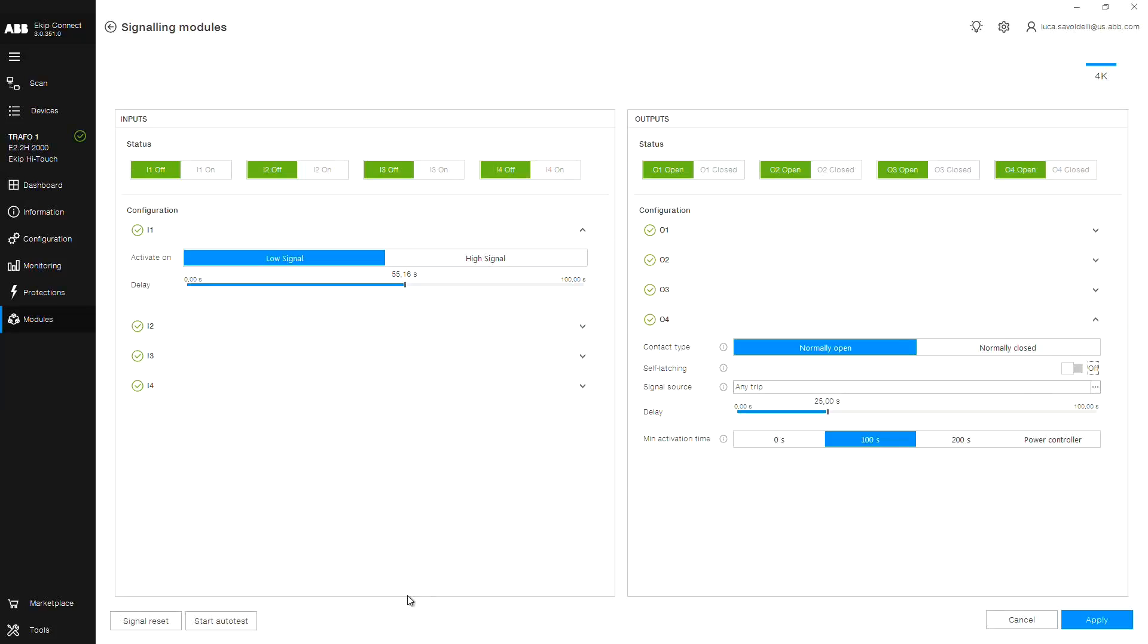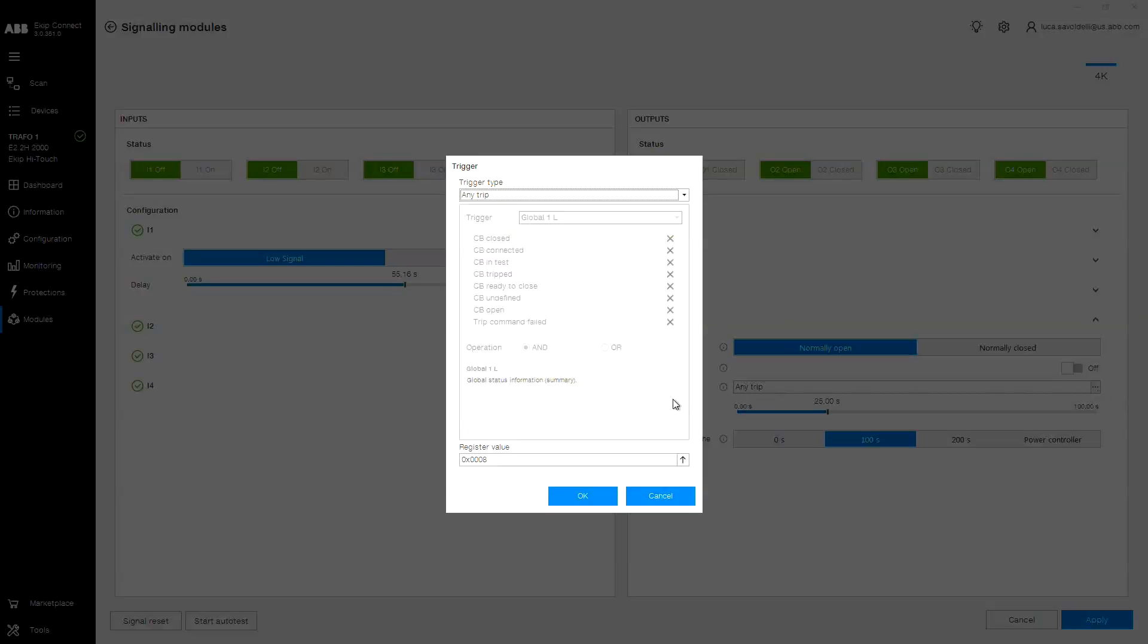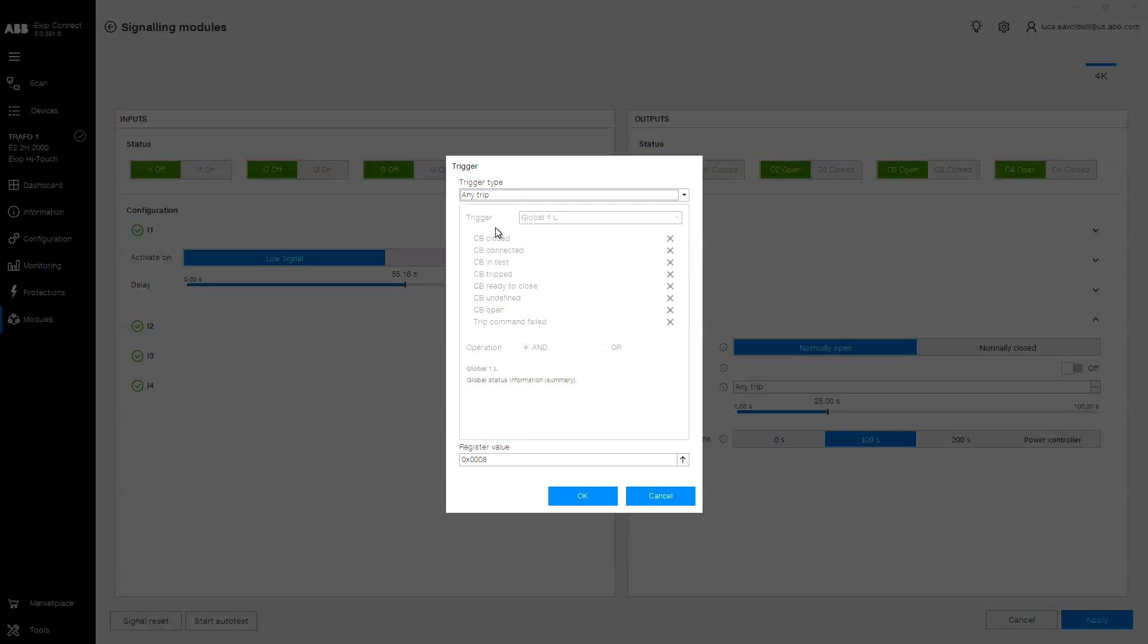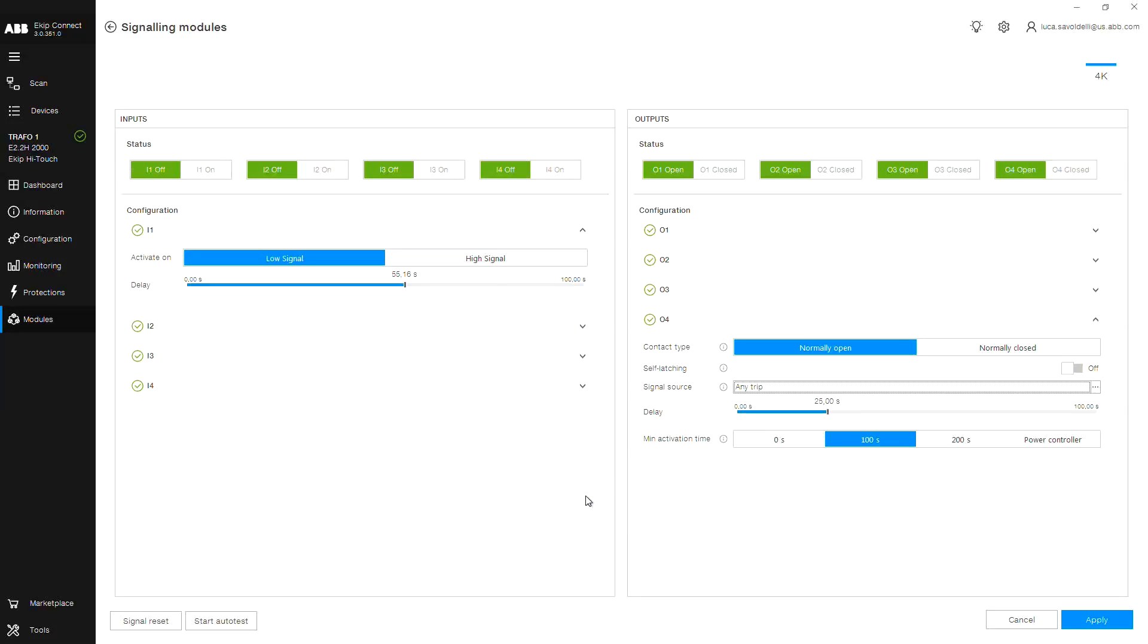Most importantly is the signal source. This is where you'll choose the type of trigger you would like to signal to an external device, such as a circuit breaker status, trips, warnings, or alarms, as well as a custom status. For this example, we will choose to signal upon any trip. Click OK.